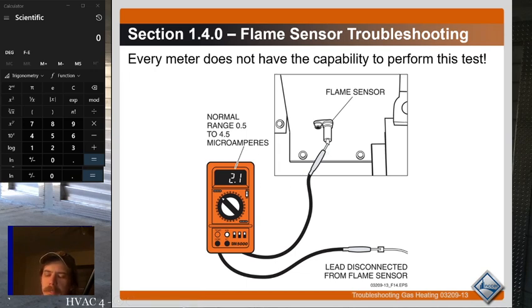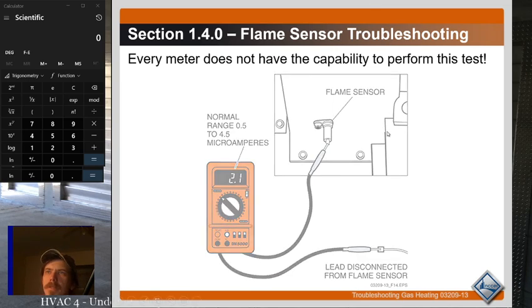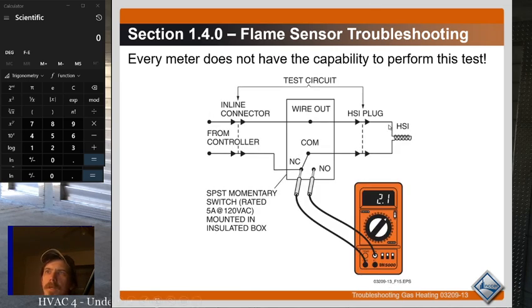Generally what's going to happen is the main burner will come on, or the pilot will come on for a few seconds, and then it'll shut right off because it didn't detect a flame signal. And it'll do that 3 times and then lock out. And if it does that, if everything seems to work, the burner comes on, then it cuts off after a couple seconds, it's either a dirty flame sensor or something wrong with that flame sensing circuit, and that's how you troubleshoot it. Every meter can't perform that test because if you don't have microamps, then it's not going to work.